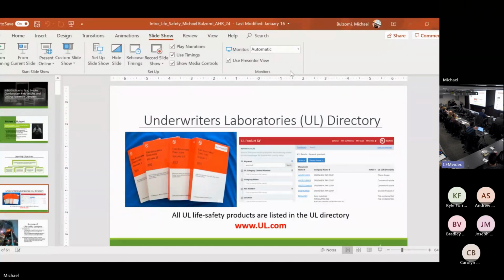But if you actually read the building code, it doesn't say dampers must be UL rated and listed. It says dampers must be tested to the UL standard. So I can take a damper and go to Intertek, which is also ETL, and do the same testing I would with UL. Just the industry wouldn't really accept an ETL fire smoke damper.